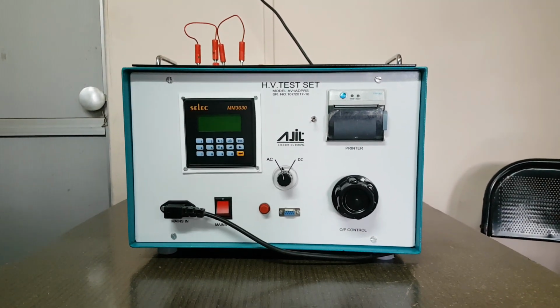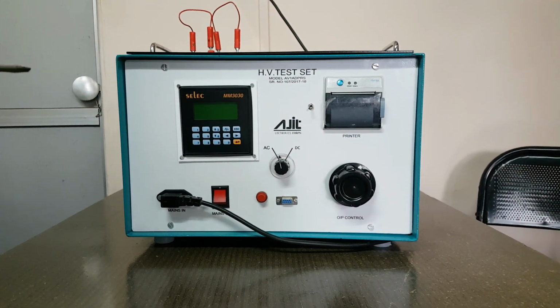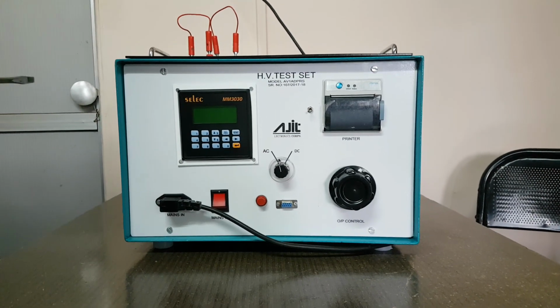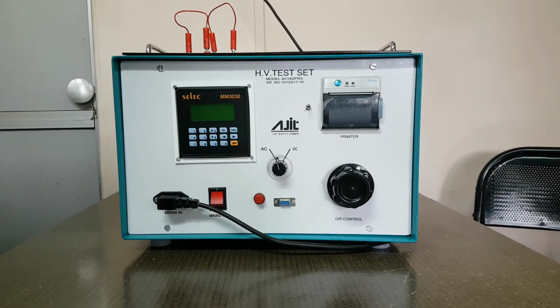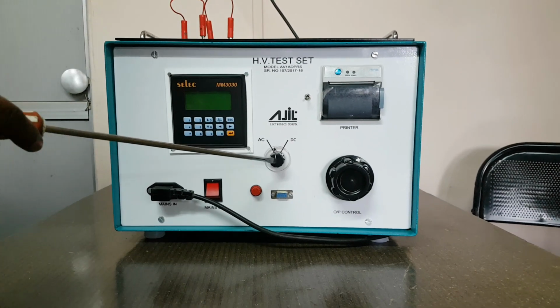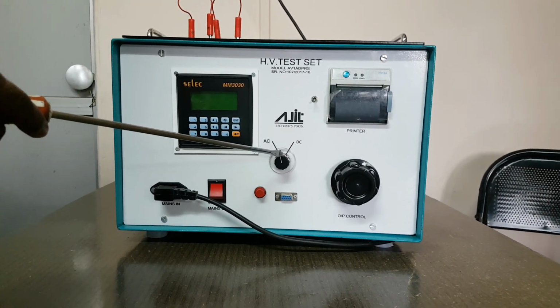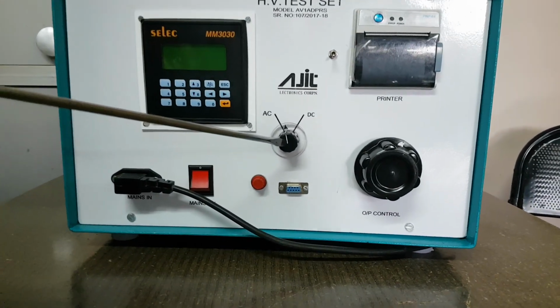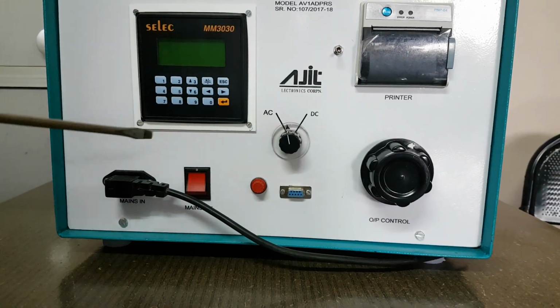This is an automatic high voltage test set having output 0 to 5 kV AC as well as DC. Here an AC and DC mode selection switch is given. From here we can set AC or DC output.